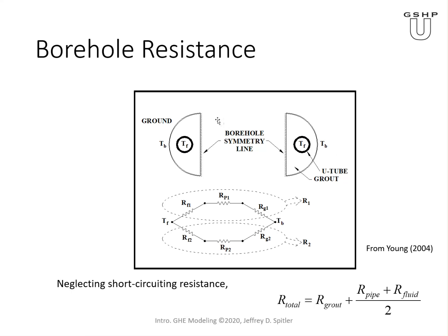A slightly more elaborate diagram shows the two halves, assuming no heat transfer between them, which is the case when we're estimating the mean fluid temperature. In that case there's the convective resistance of the inside wall of the pipe, the resistance of the pipe itself, and then the resistance of the grout between the outer edge of the pipe wall and the borehole wall. The total borehole resistance equals the grout resistance from the outside of both tubes to the borehole wall, plus the resistance of one pipe and one convective resistance inside, divided by two because there are two in parallel.